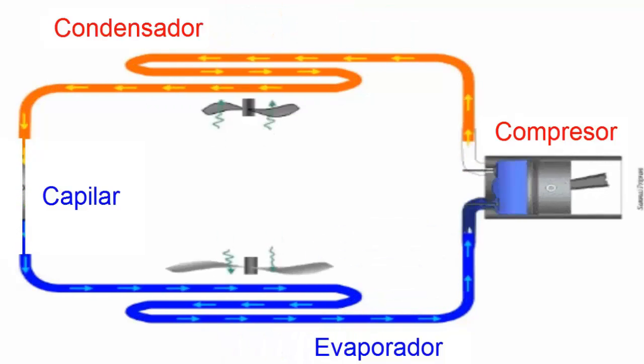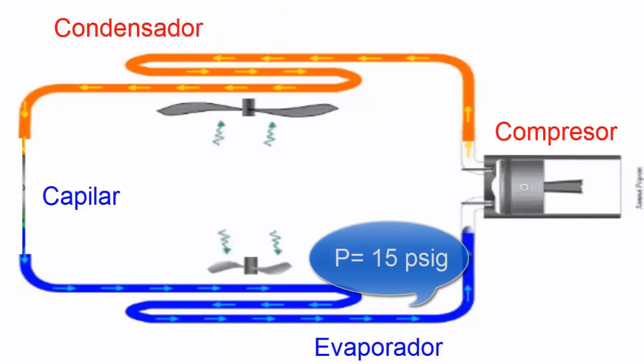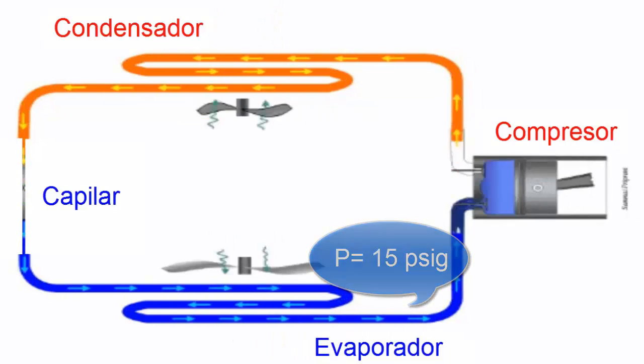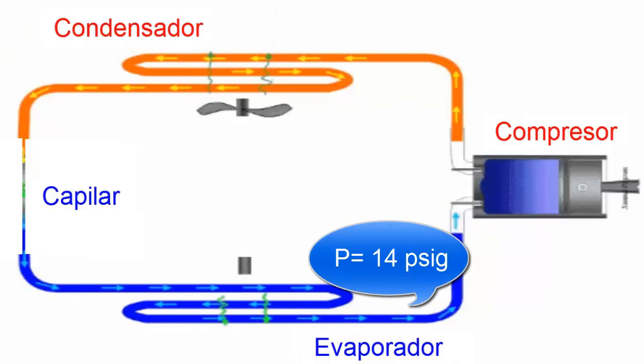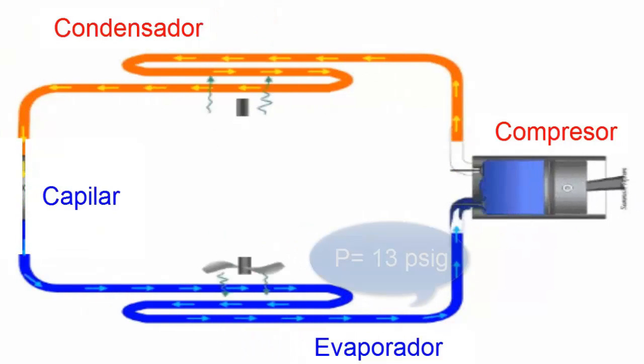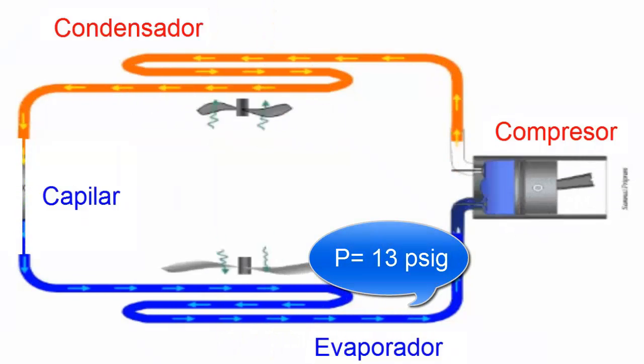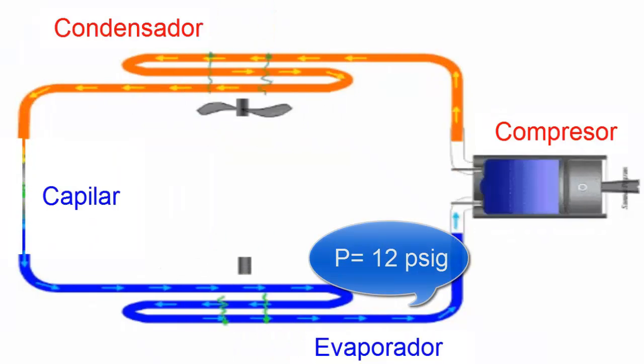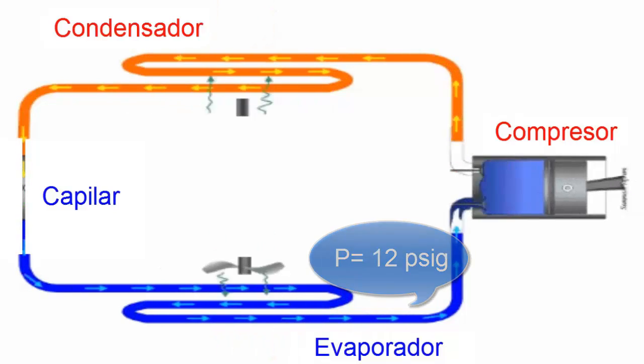2. When a partial obstruction occurs in the capillary tube, the pressure in the evaporator starts to decrease significantly. The pressure, initially 15 pounds per square inch, progressively decreases to 14, 13, and so on. This happens because there is less refrigerant available in the evaporator due to the obstruction.